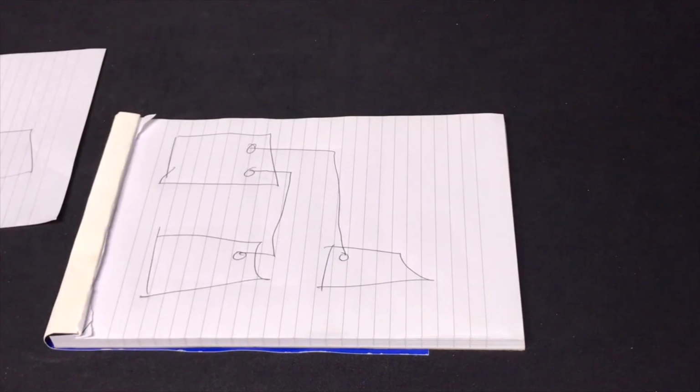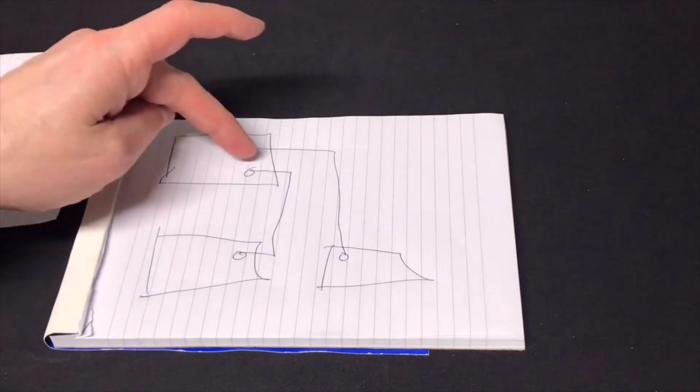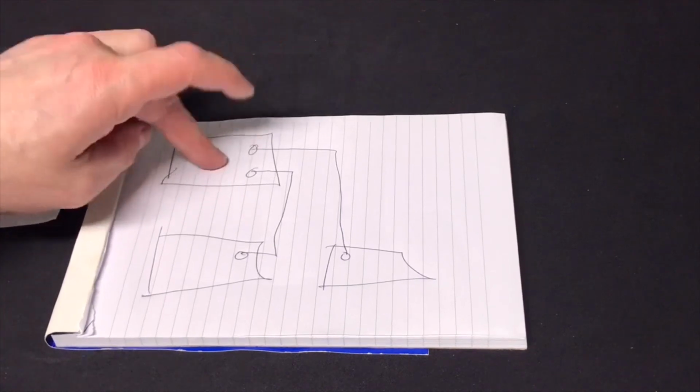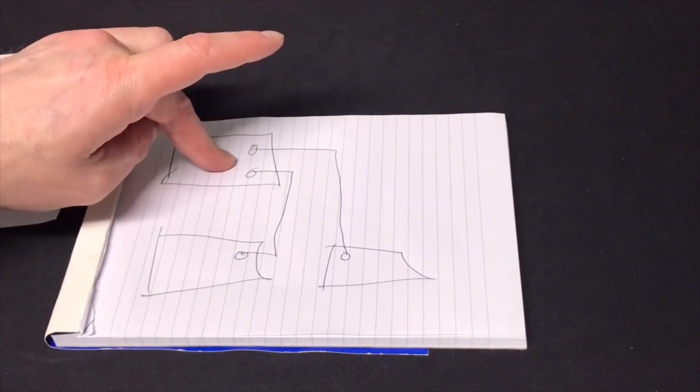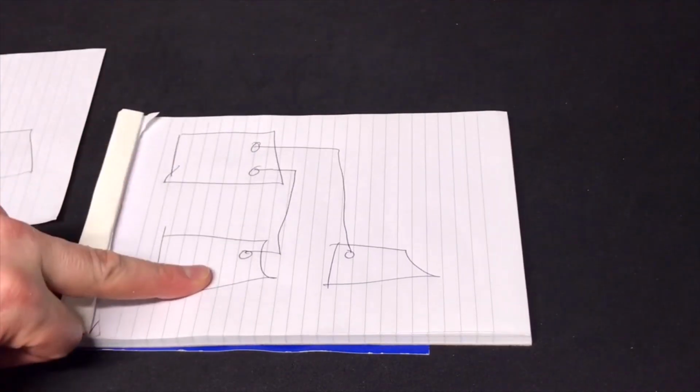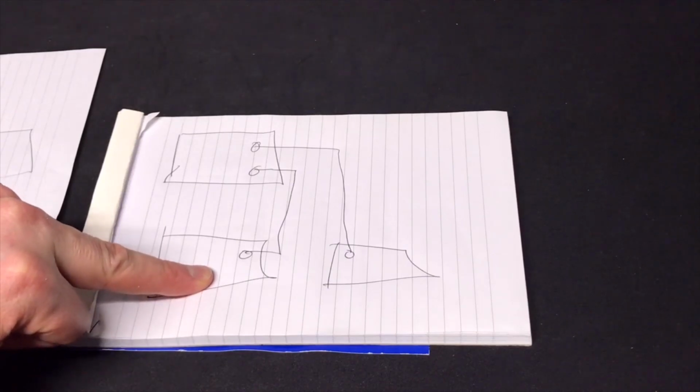But with the 1 megahertz it's a different story, because the inputs of the Marconis are actually 1 megaohm and not 50 ohms. So those you need to terminate, because the distribution amplifier is 50 ohms and the Marconi is 1 mega.